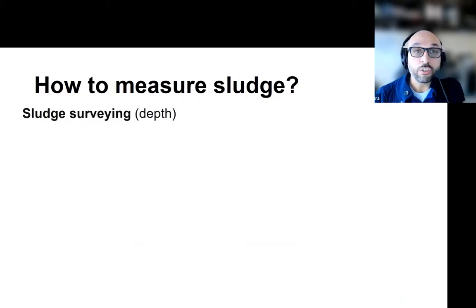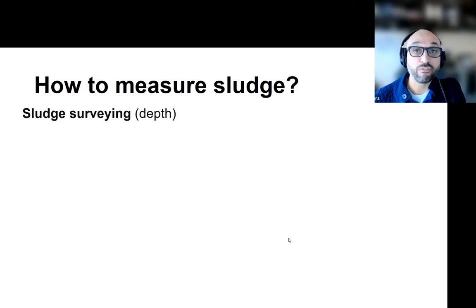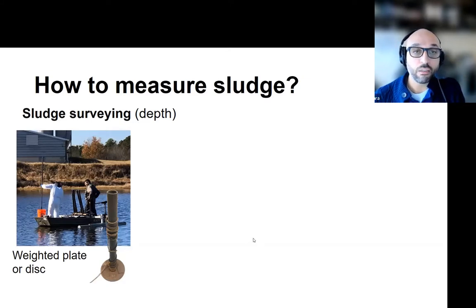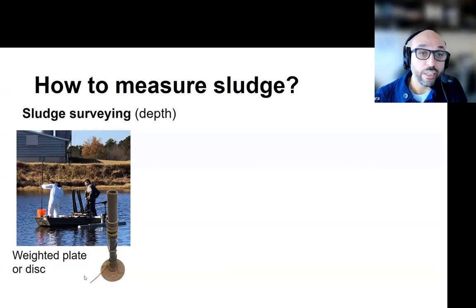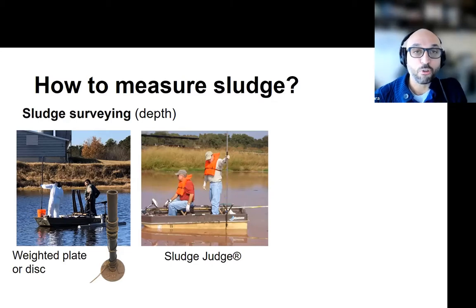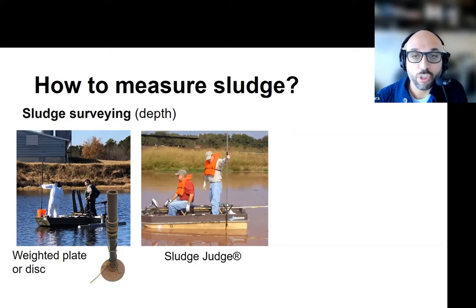We measure sludge in typically two ways. The first way is to survey, which means to determine the depth to the sludge in order to determine its volume in our structure. It's much easier if we have an open lagoon. As you can see in this picture, there is a weighted plate - the method is to determine depth all the way to the bottom, which is the liner, and then use a weighted disc to determine the depth where it settles on top of the sludge layer. Alternatively, there is a sludge judge, which is a commercial product that is essentially a large straw to collect a complete column of the lagoon and retrieve it, and using visual observation you can determine the transition from a liquid to a sludge phase.